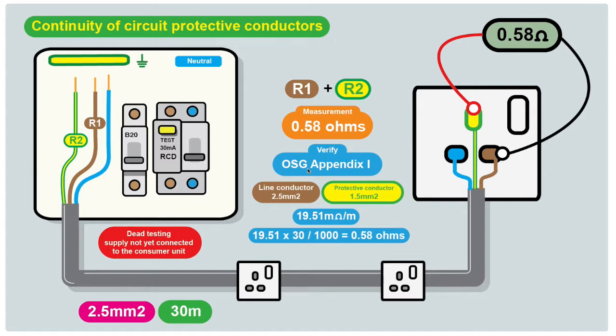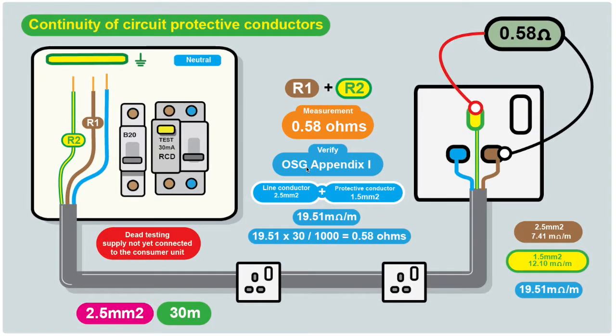We turn to Appendix I, Table I1, and there's a whole list of different conductor sizes. This list gives the cross-sectional area of both the line conductor and the protective conductor. We've used 2.5 millimeter squared twin in earth cable, and the 2.5 millimeter squared is the line conductor which has a resistance of 7.41 milliohms per meter.